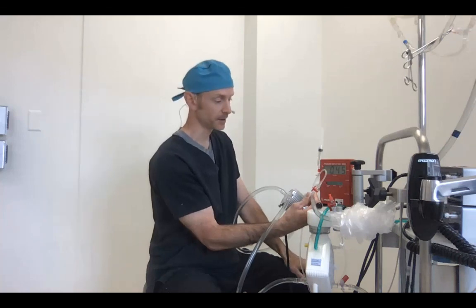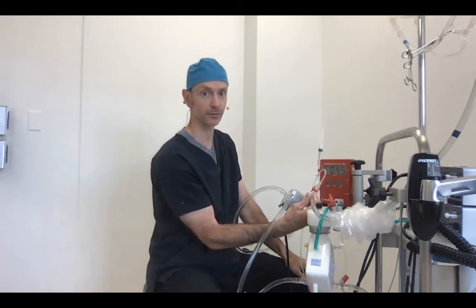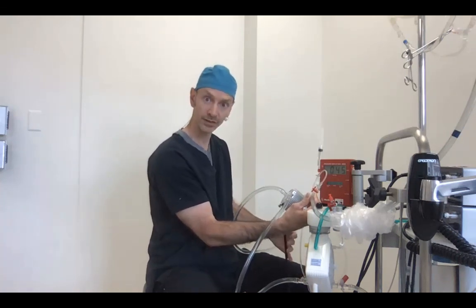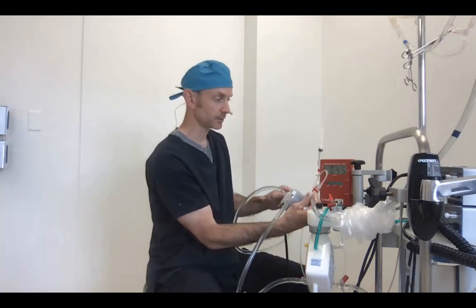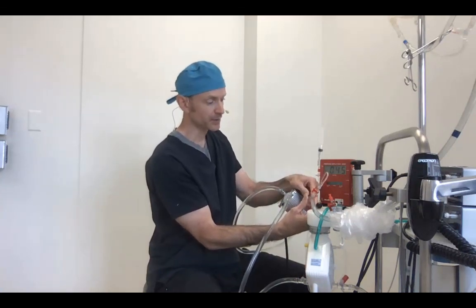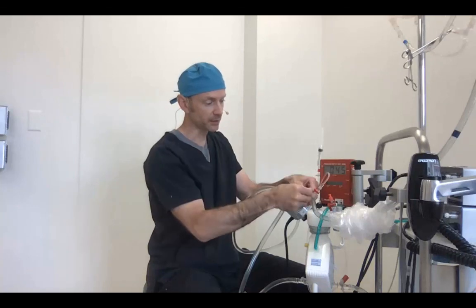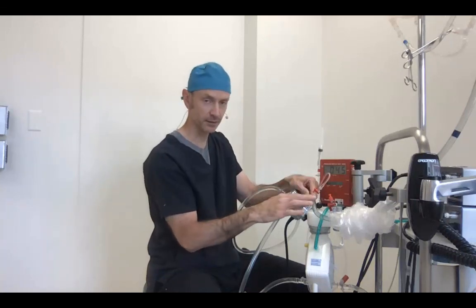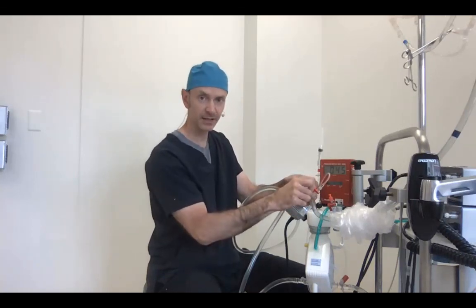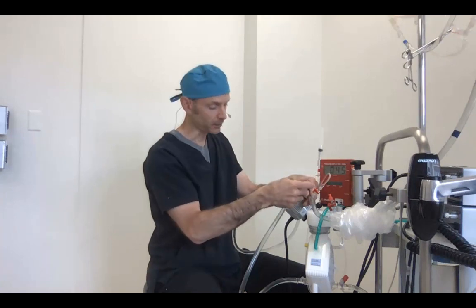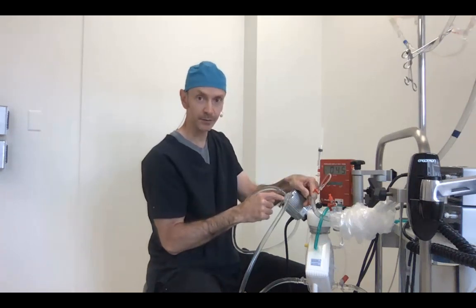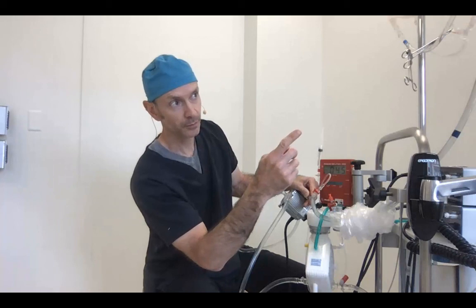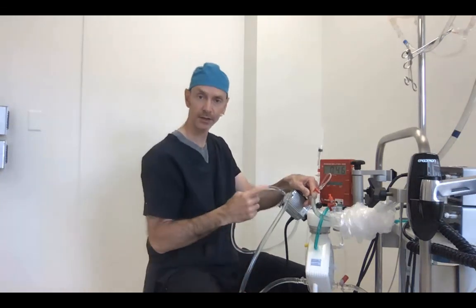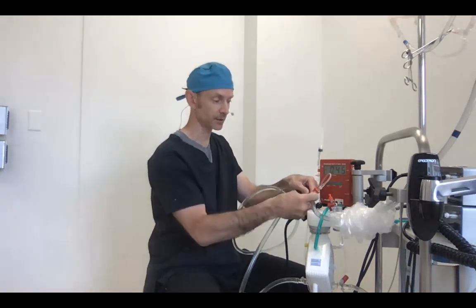There's some places that don't measure it at all, so they're going to see. They would see if they were looking very, very low pressures. So let's see how long it takes. If I had the stopcock incorporated into my venous line, and I accidentally opened it, how long until this pump deprimes? And we hear alarms over there because our flow has dropped as a result of air embolus.